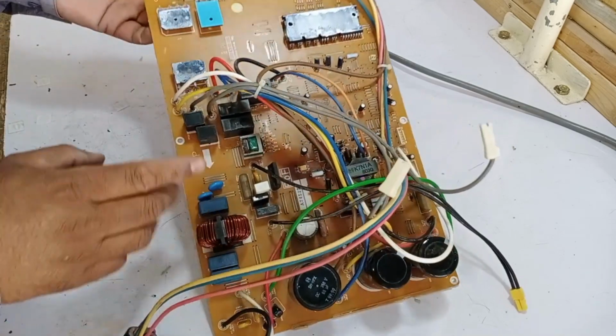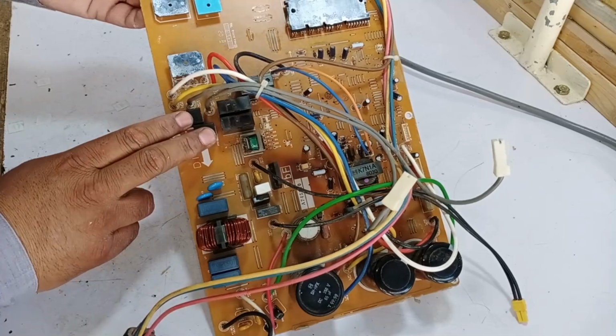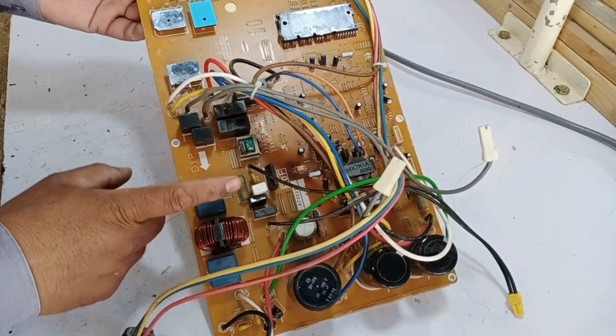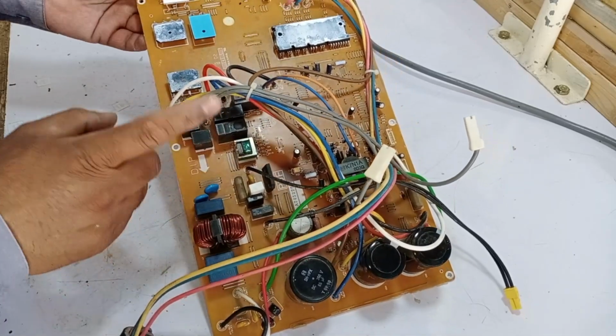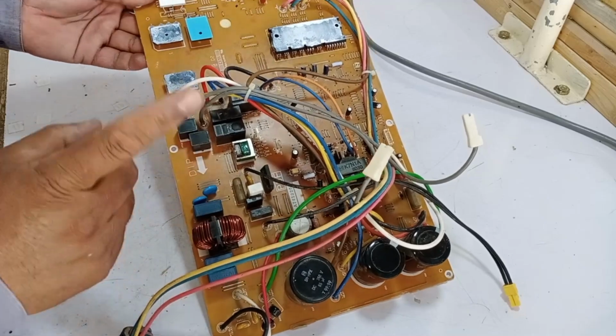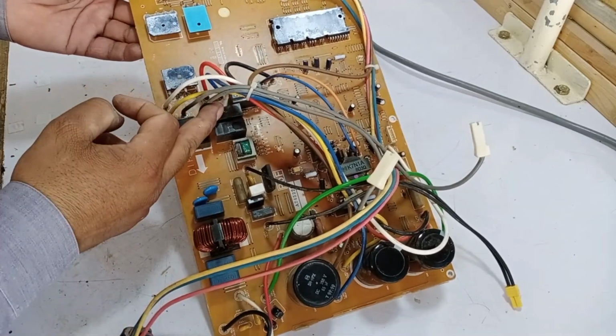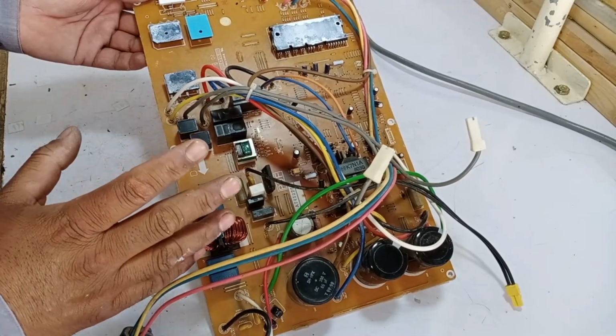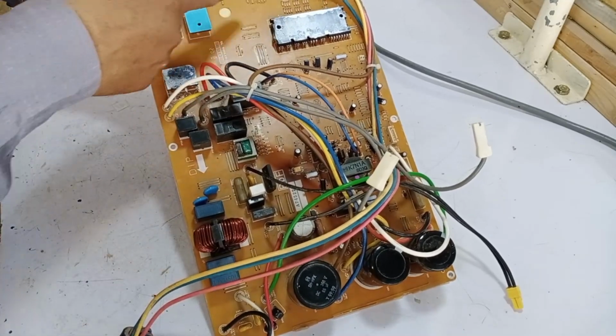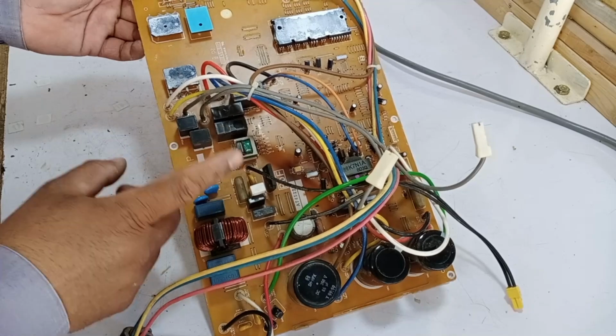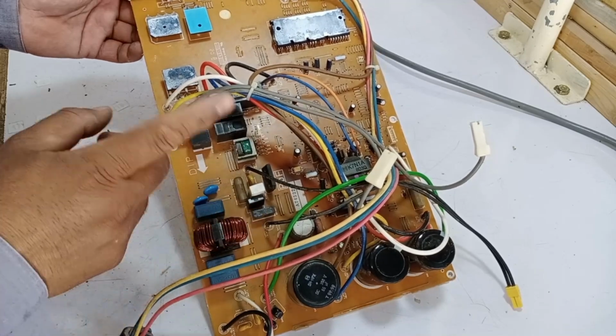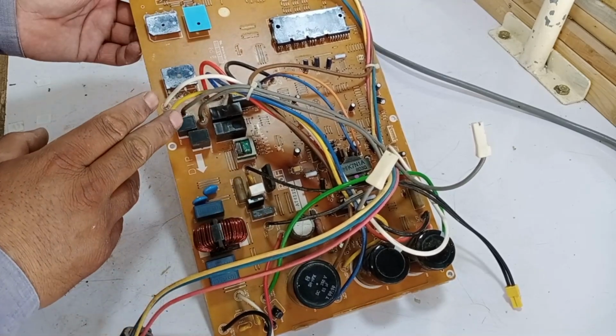Let me explain. In this system, 3 relays and 2 PTC sensors are used. When you supply power to the system without connecting the indoor PCB, only one of the 3 relays turns on, while the other 2 remain off. This is for safety purposes, ensuring the rectification circuit and IGBTs stay protected. Once the indoor unit is connected and communication is established, the system starts functioning properly.